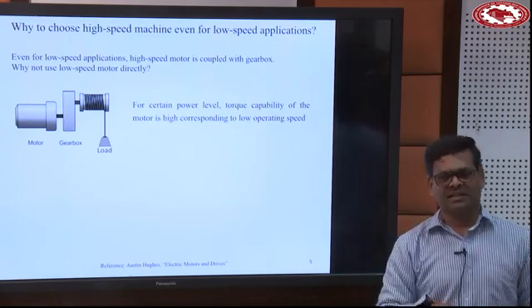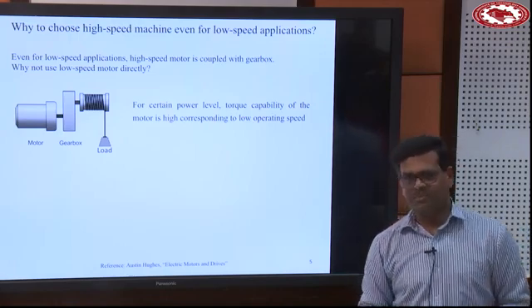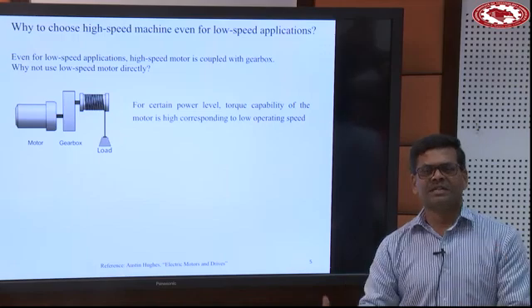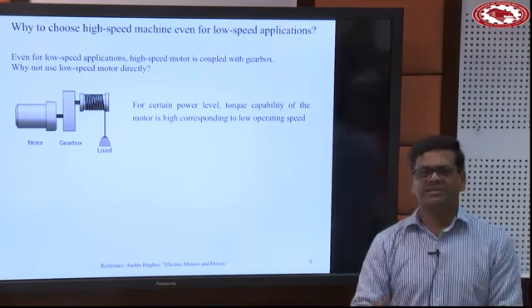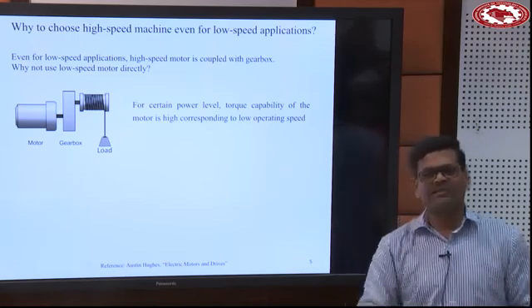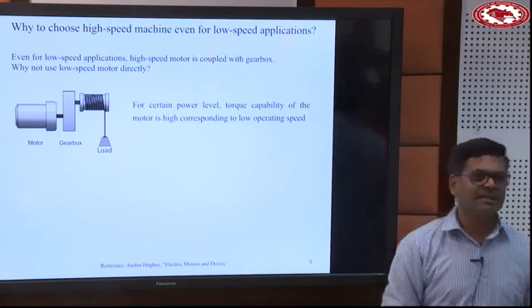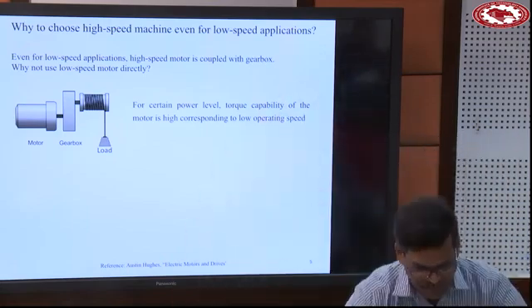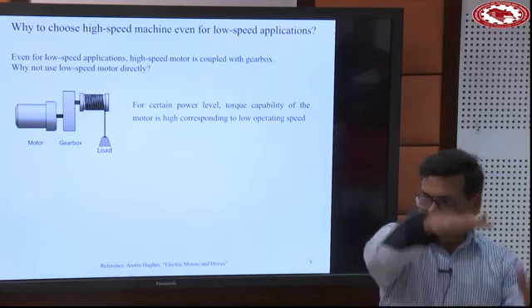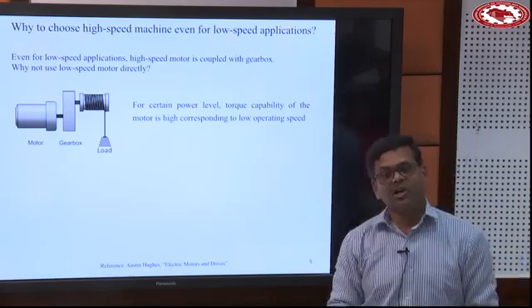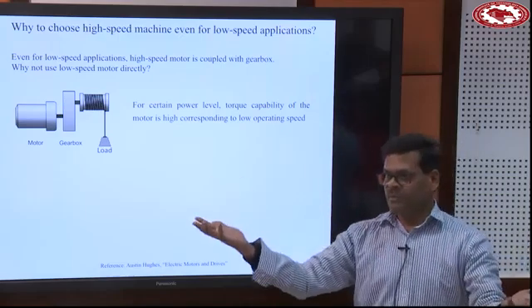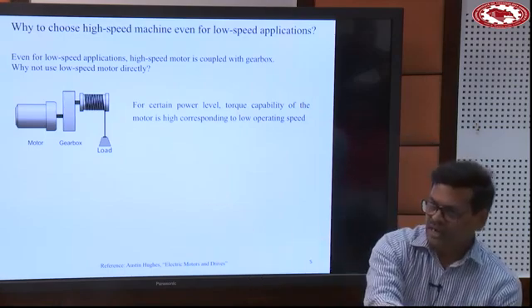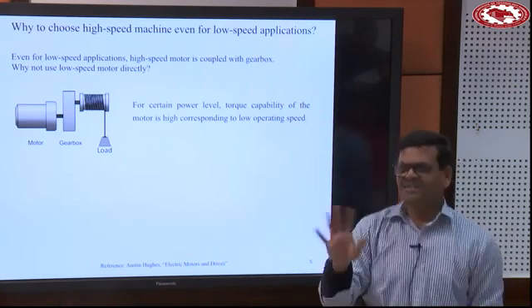There is an analogous thing in electronics also. You have some systems for low frequency, some for high frequency. For example, a 50 hertz transformer, if I say 500 kVA, 50 hertz, takes this much volume, right? Suppose I want to go for 5 kilohertz, same kVA, then the size will come down. Again 50 kilohertz, same. It's very simple.